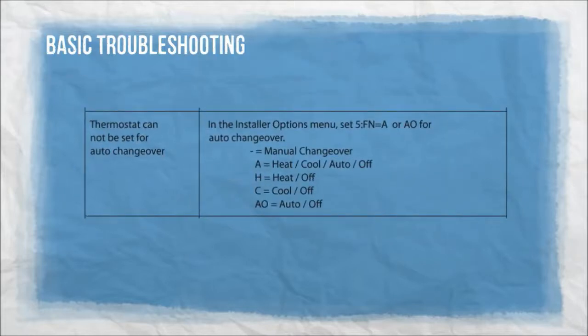Thermostat cannot be set for auto changeover. In the installer options menu, set 5FN to A or AO for auto changeover. Minus: manual changeover. A: heat, cool, auto, off. H: heat, off. C: cool, off. AO: auto, off.